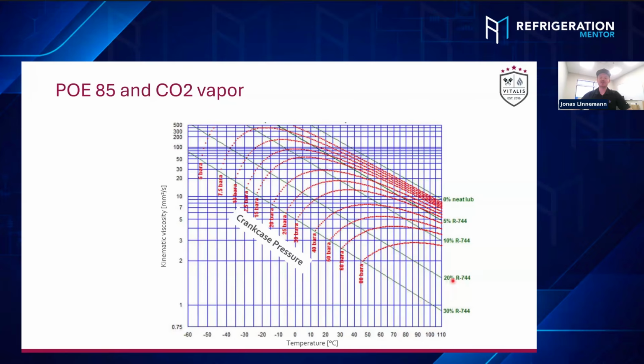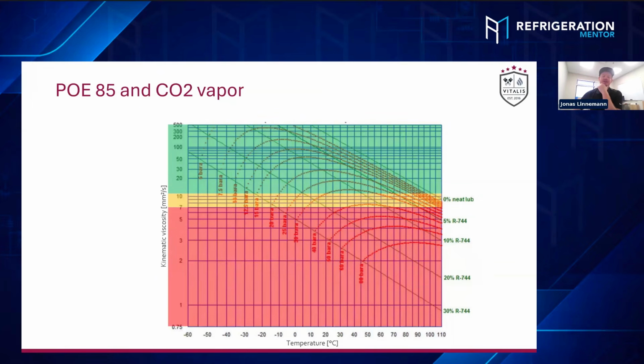And also you can see these lines, how much CO2 is actually dissolved in the oil. So this one is 100% oil, or 0% CO2. And then with the higher pressures here, it all goes up to a higher CO2 saturation. To get that in a little relation, what's good, what's bad, I put some colors over it. So typically you want to stay above 10 centistokes, which is a very good lubrication level for the oil inside the compressor. And below 7, you definitely can't lubricate the compressor anymore. So you have a green, yellow area, and you want to stay outside of the red area.